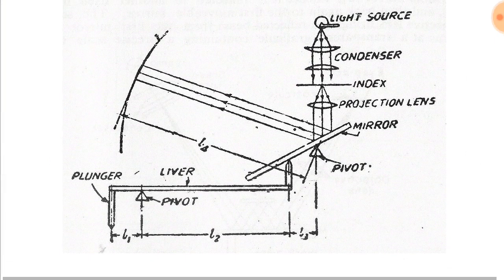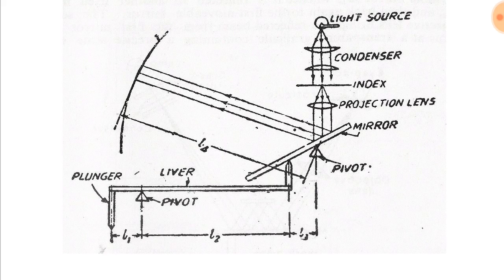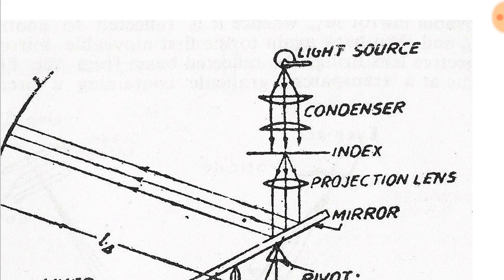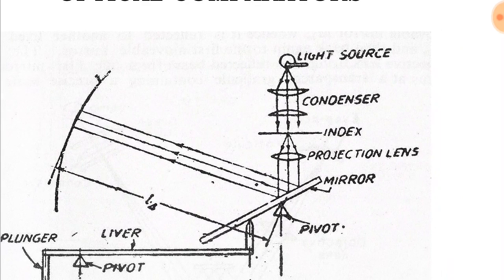The image of an index is projected on a scale on the inner surface of the ground glass screen. Optical magnification provides a high degree of measuring precision due to reduction of moving members and better wear resistance qualities. Optical magnification is also free from friction, bending, and wear.